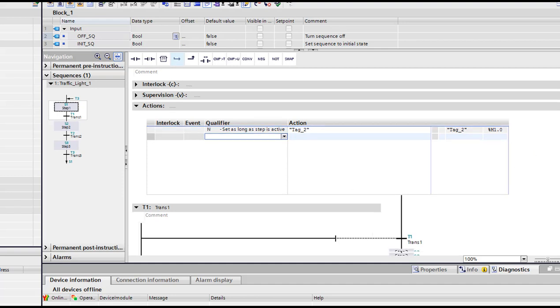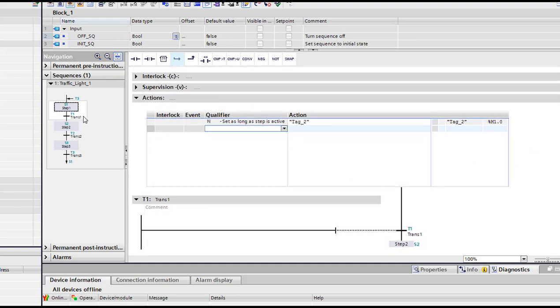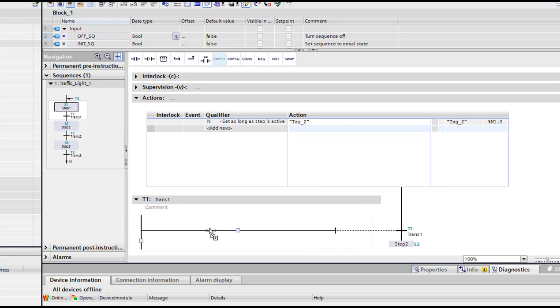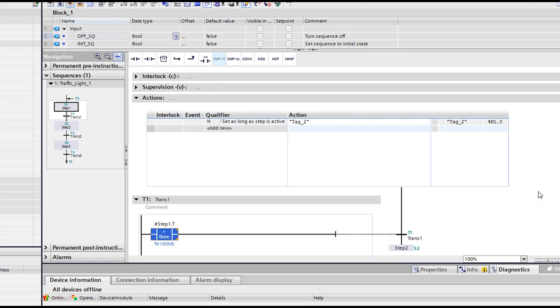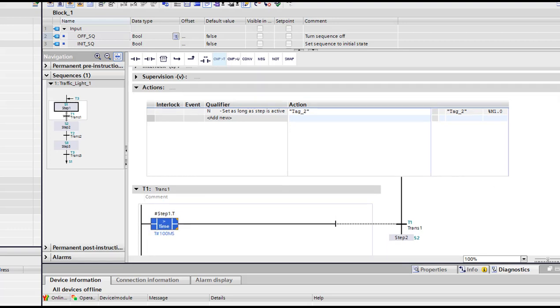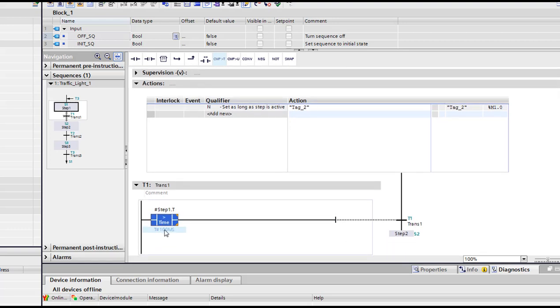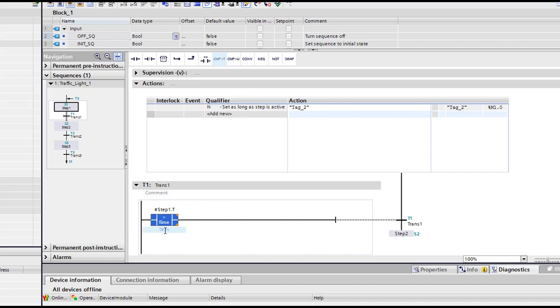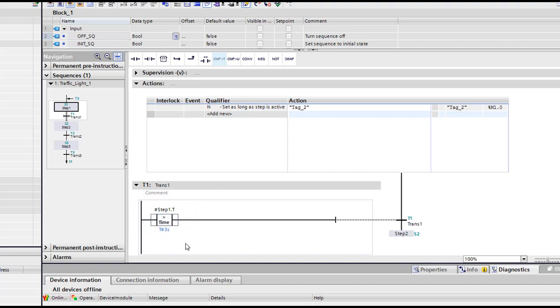Then here I'm gonna add the condition to pass to green. I'm gonna just wait a time, just time condition. Like wait for, here they are 100 milliseconds, we're gonna use maybe three seconds. I'm gonna just write 3s here. So what happens is the action stays activated until here the time passed three seconds. So when we pass here is activated, it waits three seconds until to pass to the other step. It's simple use of the timer here, it's important to use it in projects.